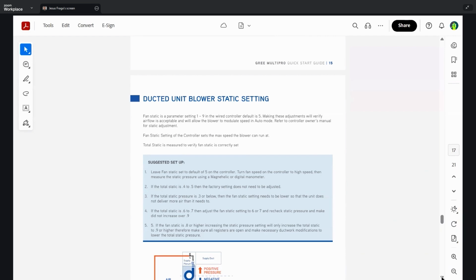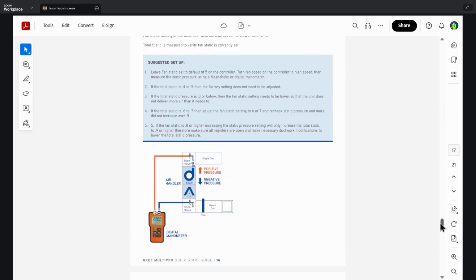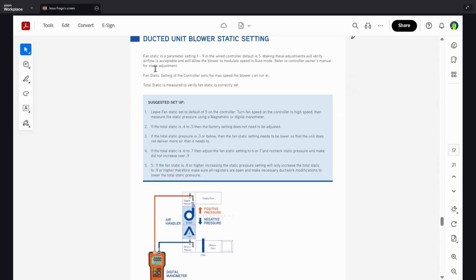So continuing here, the ducted unit static pressure. Similar to the 410A, there are 9 static pressure settings in the wired controller. The units are default for 5, so make sure that you're taking your static pressure across the air handler and adjusting as needed. We recommend that the total static pressure be within 0.4 to 0.5 inches of water column. Anything below or above that will need to be adjusted. So as long as you're within that 0.4 to 0.5, you're good.